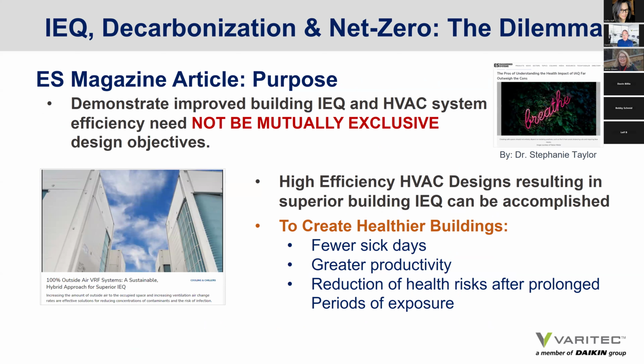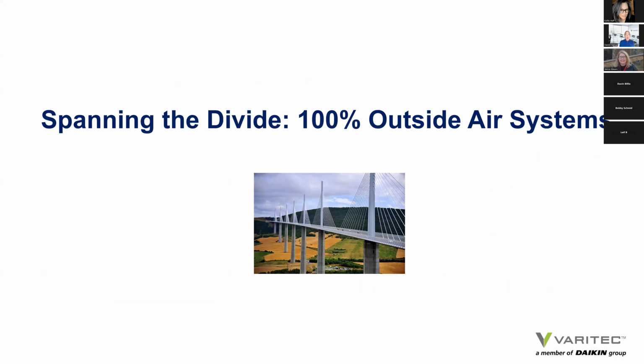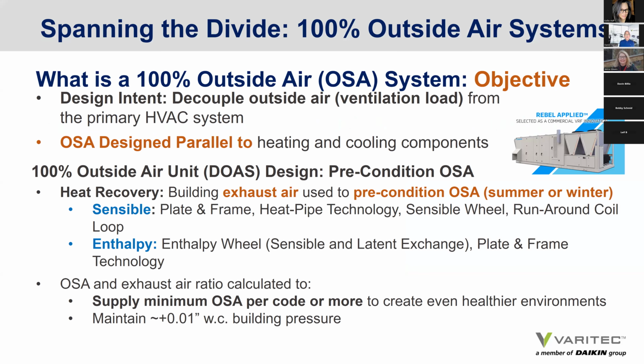This challenge and this dilemma inspired me to examine 100% outside air variable refrigerant systems to demonstrate that good indoor environmental quality, good indoor air quality, and system efficiency need not be mutually exclusive. And we can achieve more efficient HVAC MEP designs while we're creating better indoor environmental quality, providing we bring the right pieces together in a system solution design. So, spanning the divide, let's look at 100% outside air systems. And what are 100% outside air systems?